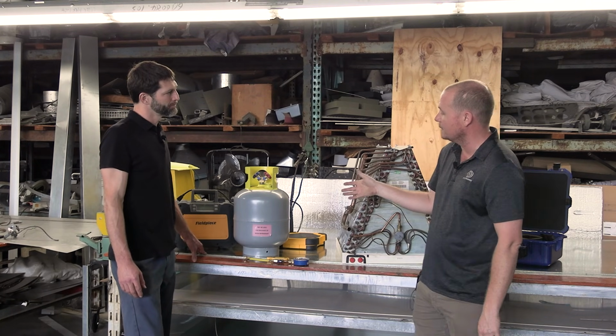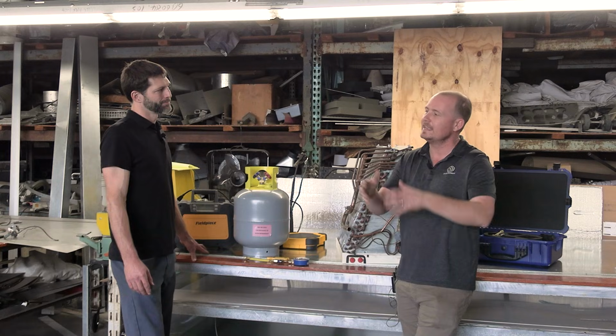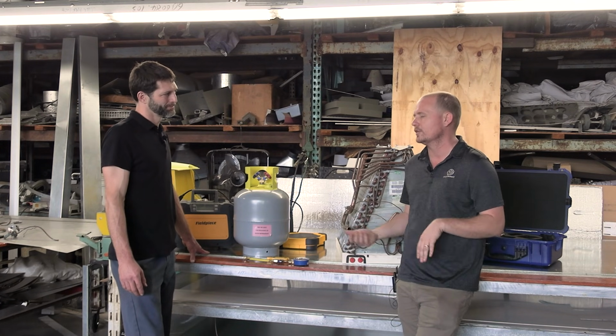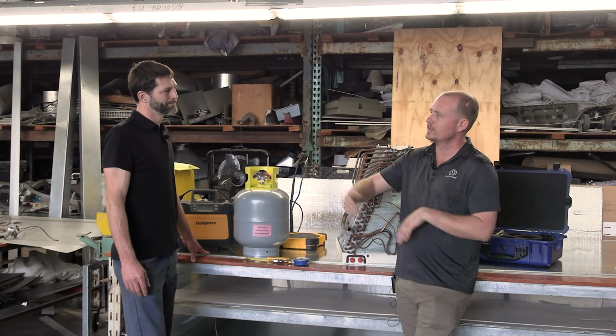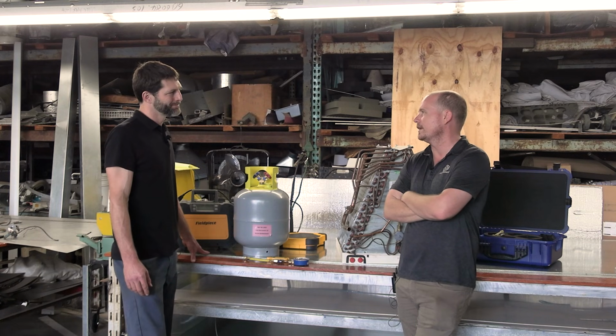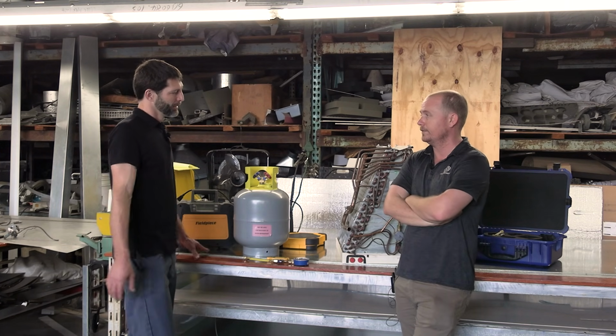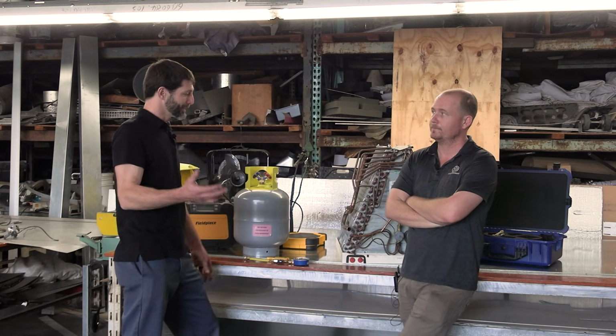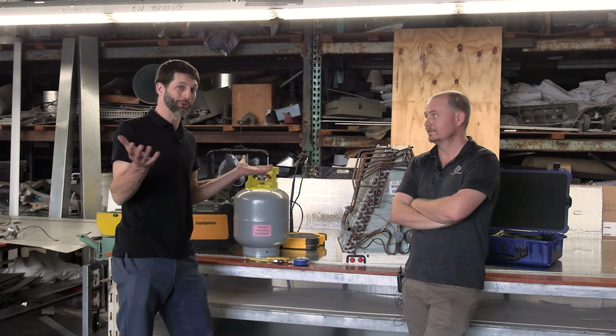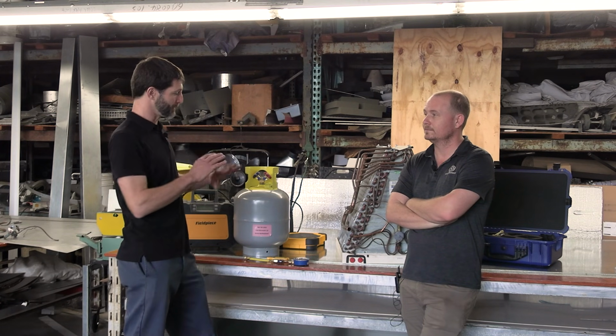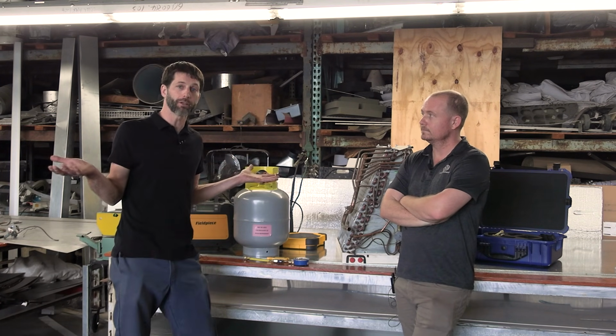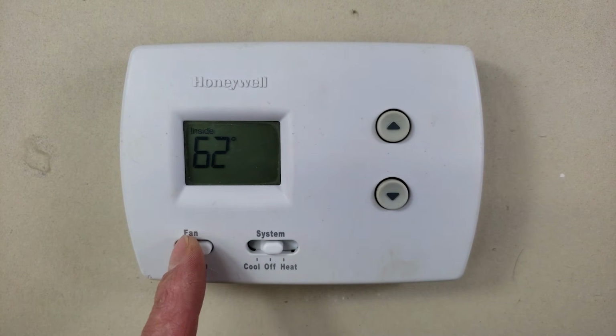Are there cases where it might be advantageous to heat some things in order to try to get some refrigerant out? Maybe. And you actually talked about this a little bit in terms of running the blower as well, which is another really good thought. Yeah, inside the building, it's usually above 32 degrees. Especially if it's conditioned all the time, you're going to be around 70 degrees. So you can run the fan. I always advocate, hey, run the fan during a vacuum.